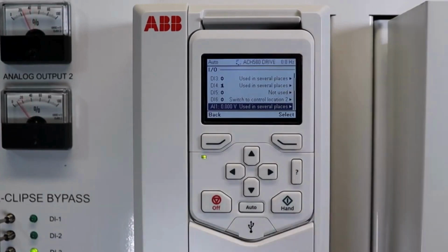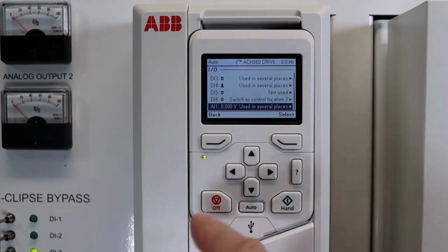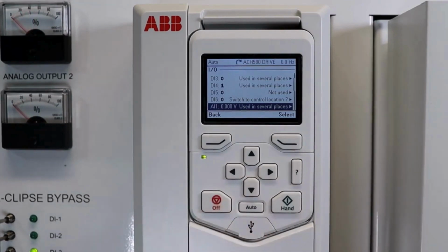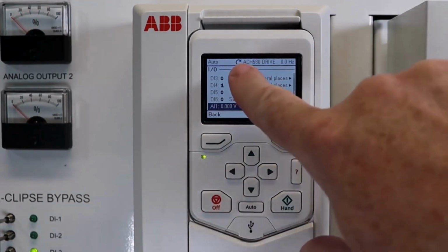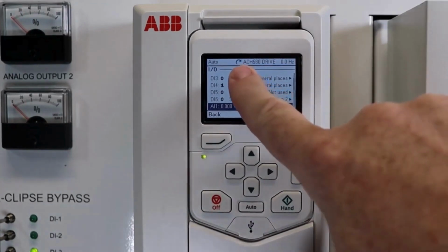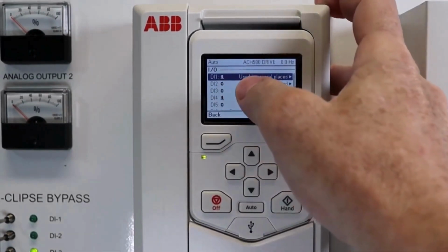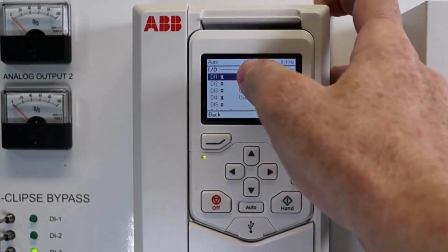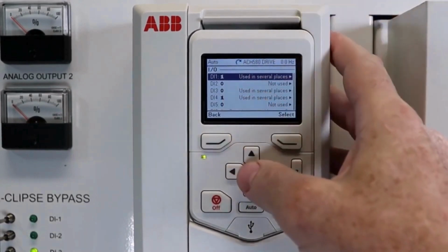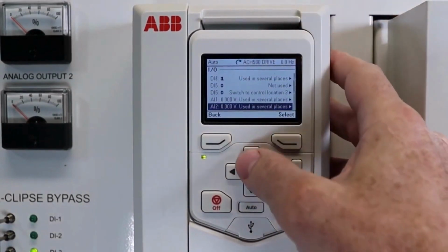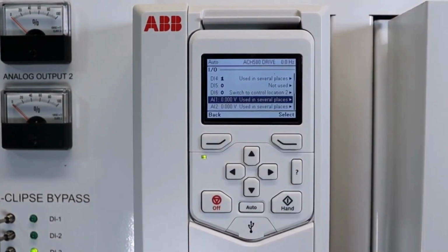Let's say I'm being told that I have a 5 volt input and the drive is not operating, okay? And the drive turns on. See, right now the drive's not turning, the arrow shows the drive is off. I'm going to turn the drive on again. And actually what I'm doing is I'm turning on DI1. DI1 is my start source right here. The drive is blinking, but there's no speed reference. And so I'm going to go down, look at our analog input, and say, hey, we have 0 volts at the analog input. Well, no, we're sending you 5 volts. We know we are, and that's what we hear. Okay, let me check this real quick.